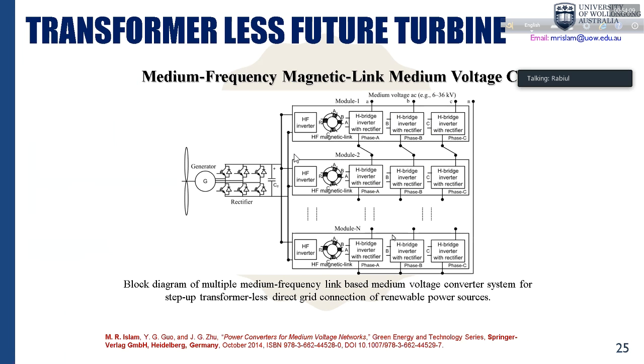So I already modified the concept to increase the power handling capacity. Here you can see I proposed this modular concept: from the low voltage side they are connected in parallel, and each module has its own individual high frequency magnetic link. So each high frequency magnetic link now handles maybe just 100 or 200 kilowatts.